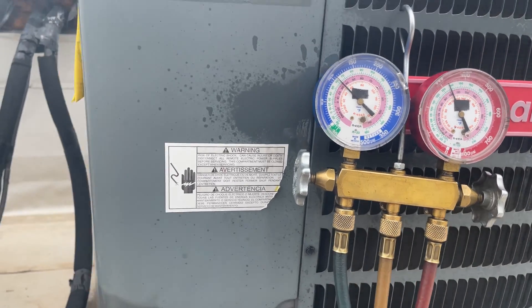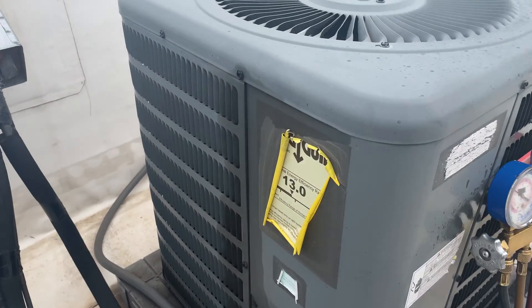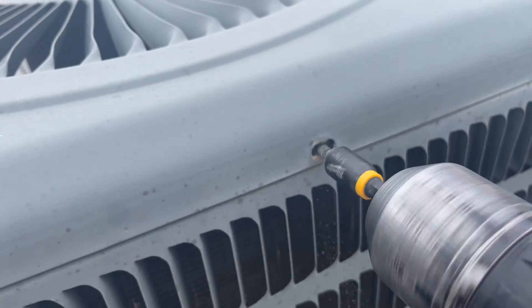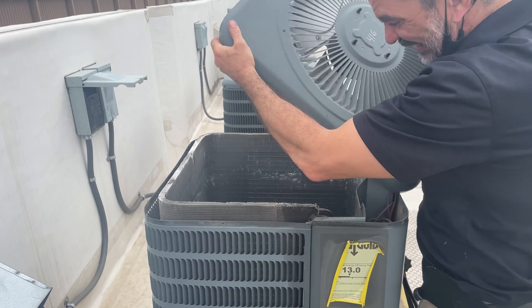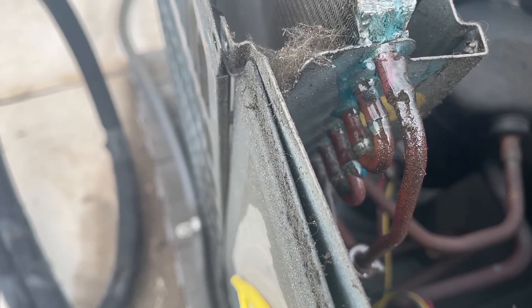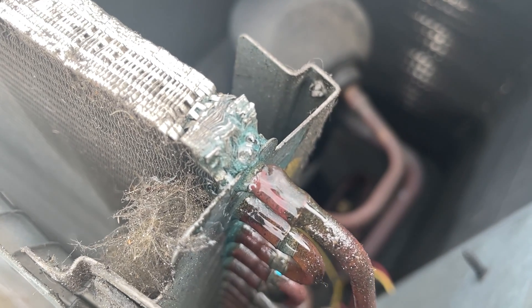You may be asking why this tech isn't doing a subcool or superheat check — damn right I'm not, I'm replacing this thing tomorrow. But just so we're clear, I want to verify that this thing is leaking, even if this giant sign of oil isn't enough. This thing is just dripping with oil. Every single time, same spot.